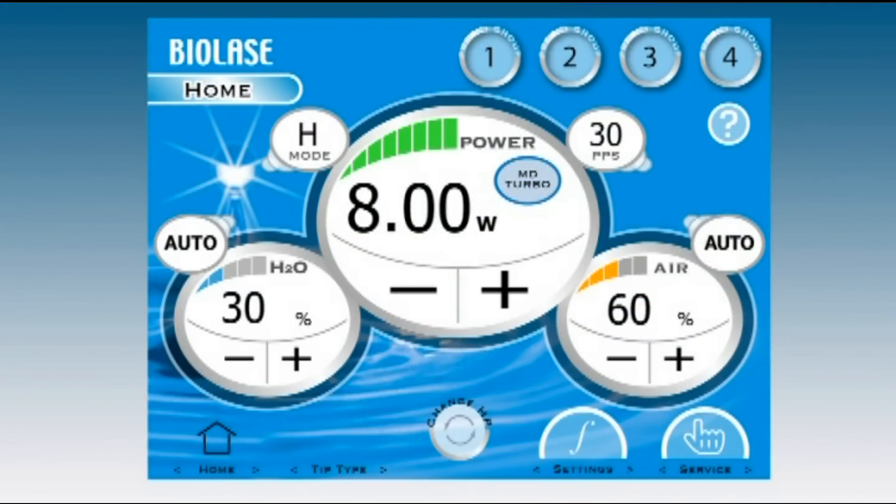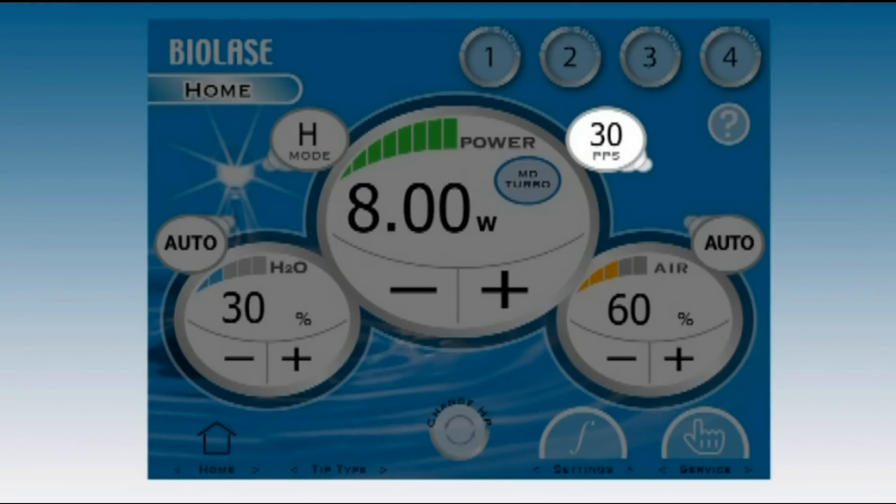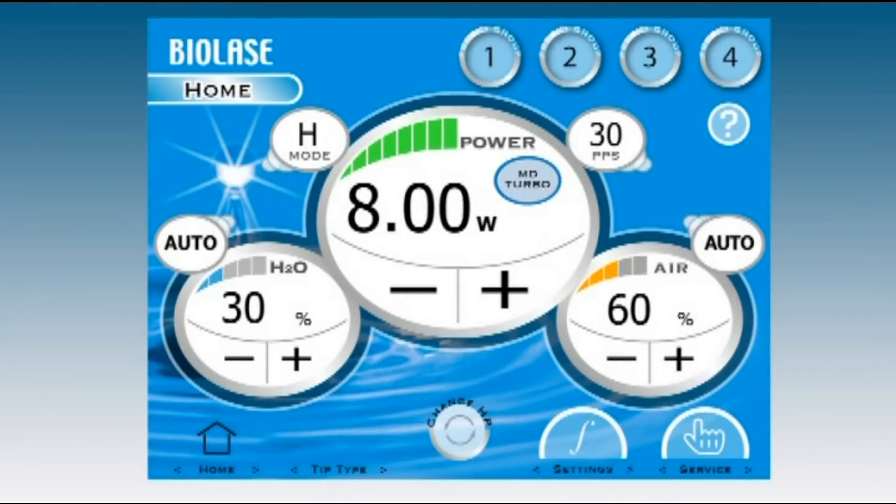No matter what procedure you're performing or tissue type you're operating on, Waterlase gives you complete control with four settings: power, frequency, air and water spray, and pulse mode. When you understand how each of these settings affects cutting, the laser is simple to use.